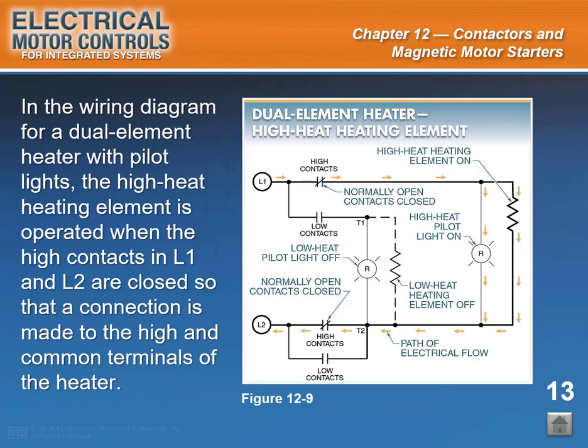Slide caption: in the wiring diagram for a dual-element heater with pilot lights, the high-heat heating element is operated when the high contacts in L1 and L2 are closed so that a connection is made to the high and common terminals of the heater. See figure 12-9. To operate the high-heat heating element, the high contacts in L1 and L2 are closed so that a connection is made to the high and common terminals of the heater. This allows the high-heat heating element to be energized. A low-heat pilot light and high-heat pilot light turn on to indicate each condition because each pilot light is in parallel with the appropriate heating element. End of slide 13. Start of slide 14.